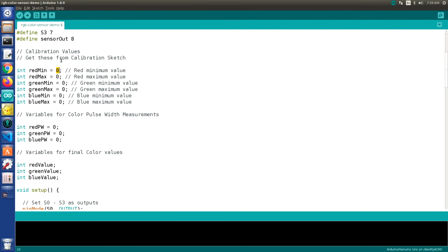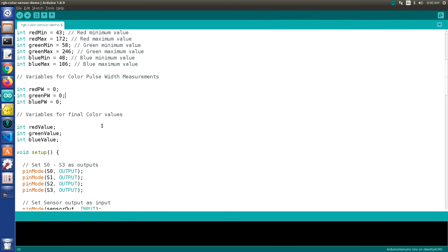Okay, the red min that I got was 43, and the red max that I received was 172. The minimum green pulse width was 58, and the maximum was 246. And finally for the blue, I had 48 as my minimum and 186 as my maximum. Okay, and again you'll want to modify that with your own calibration values.